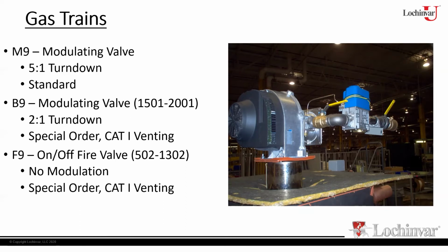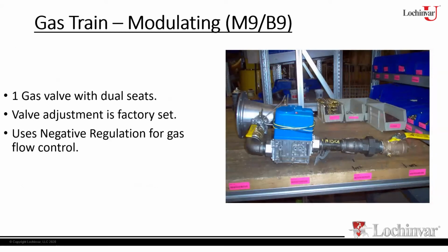Now, as far as our gas trains, the M9 and your B9 is going to consist of basically 2 components, a venturi and the gas valve itself, the modulating gas valve. I'll get it out in a second. Now the valve will change based on the size of the heater. Anywhere from what we call the blue top gas valve here, which is a Honeywell valve, up to the larger models where you get into the Dungs valves. So basically, you're going to have that modulating valve there, and then you're going to have a separate venturi, which is connected to the inlet or the suction side of the blower. And that's what's inducing that vacuum on the gas valve.